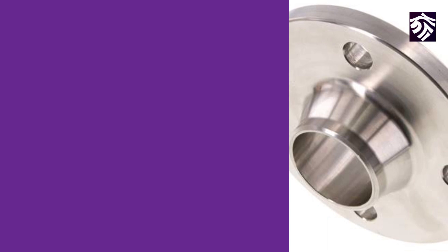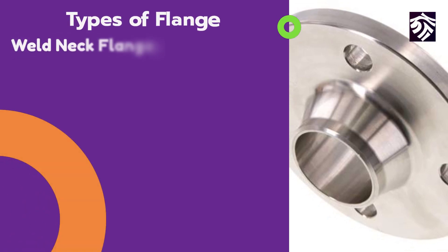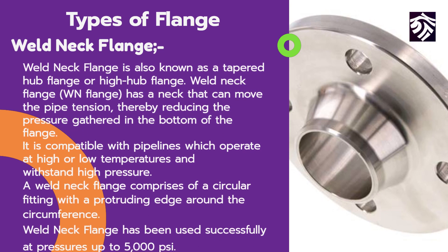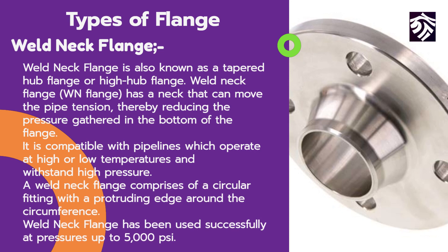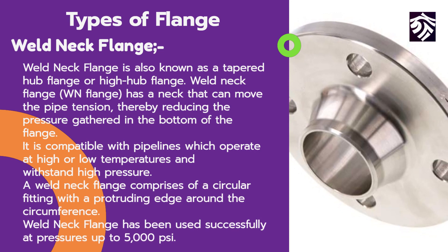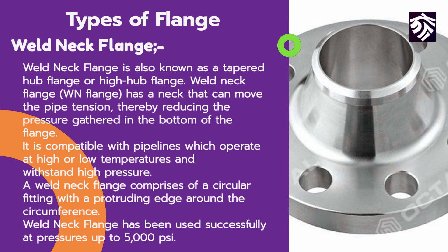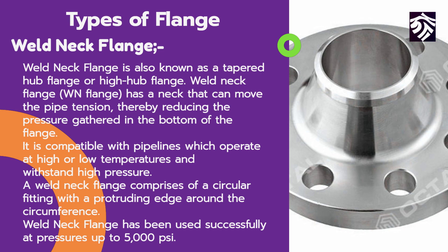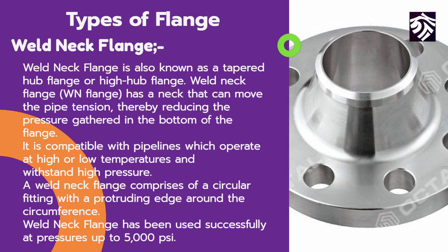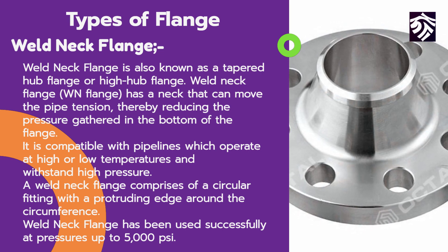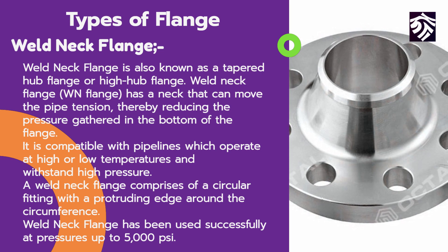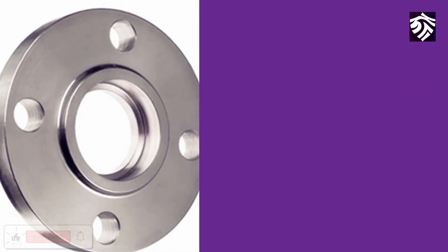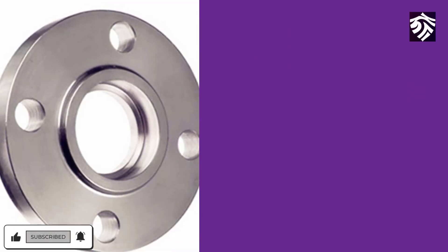Another type of flange is the weld neck flange, also known as a tapered hub flange or high hub flange. The weld neck flange has a neck that can move the pipe tension, thereby reducing the pressure gathered at the bottom of the flange. It is compatible with pipelines which operate at high or low temperatures and can withstand high pressure. A weld neck flange comprises a circular fitting with a protruding edge around the circumference, and has been used successfully at pressures up to 5,000 pounds per square inch.